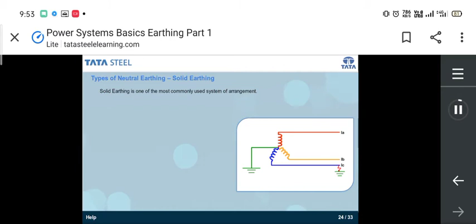Solid earthing is one of the most commonly used system arrangements. In this type of grounding, the star point is directly connected to the ground, as you can see in the diagram here. Solid earthing has many advantages. Firstly, in this type, fault current completely nullifies the effect of capacitance current. Hence, there is no arcing ground.